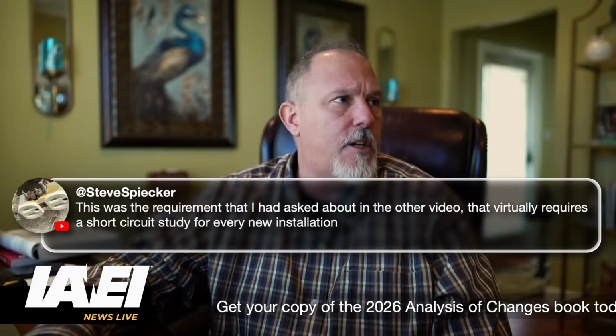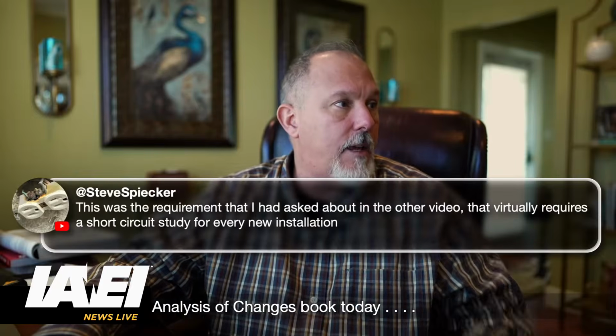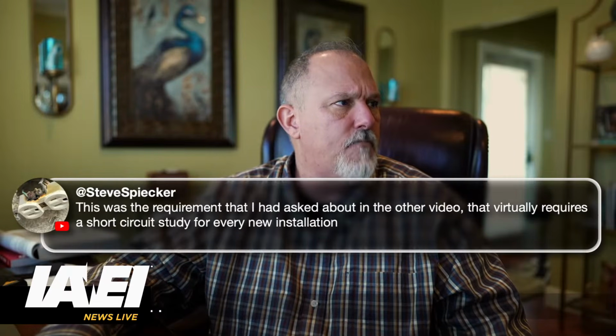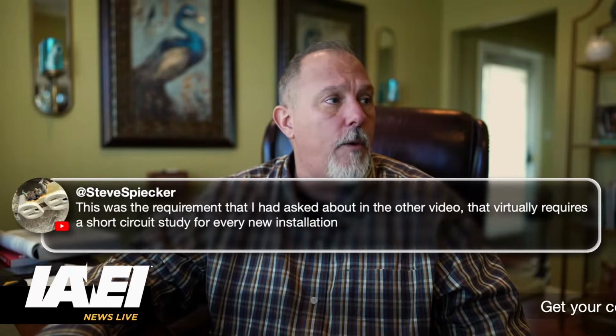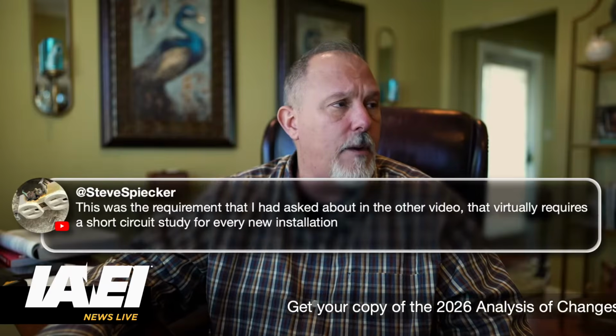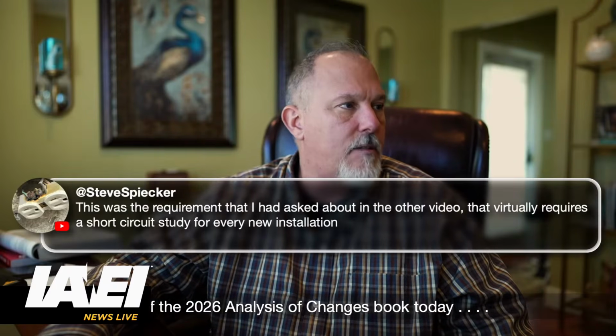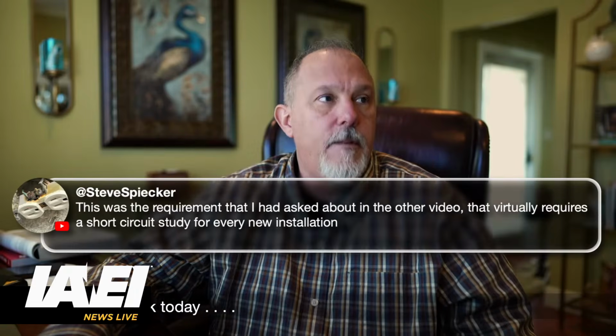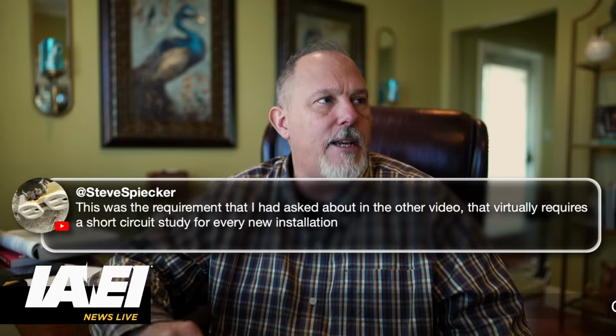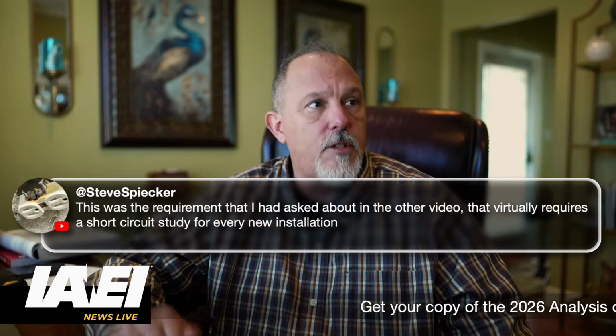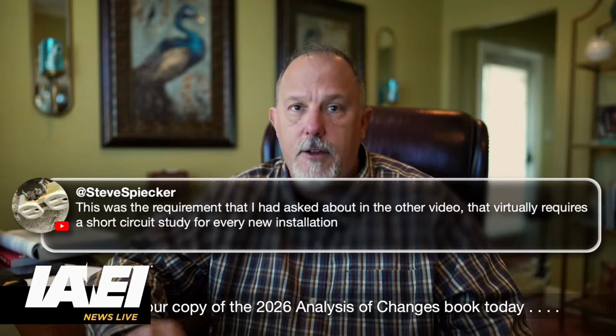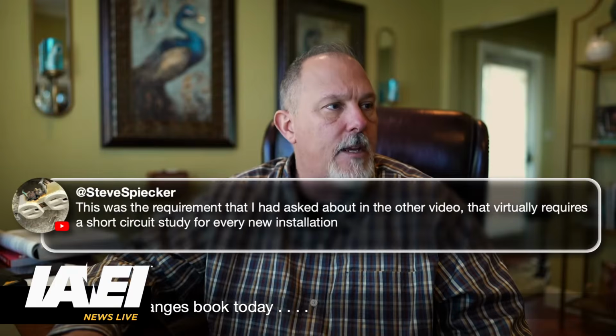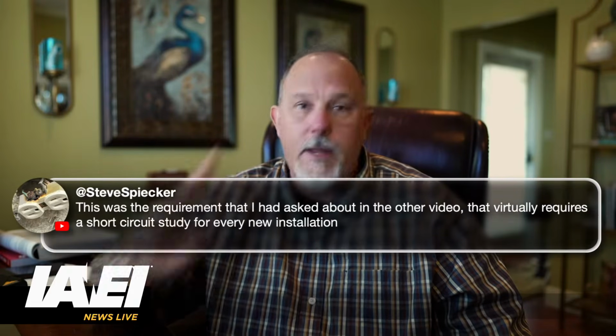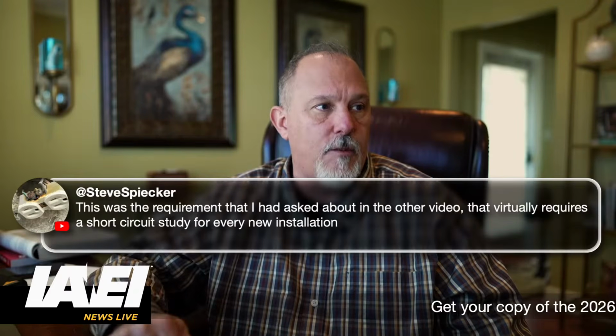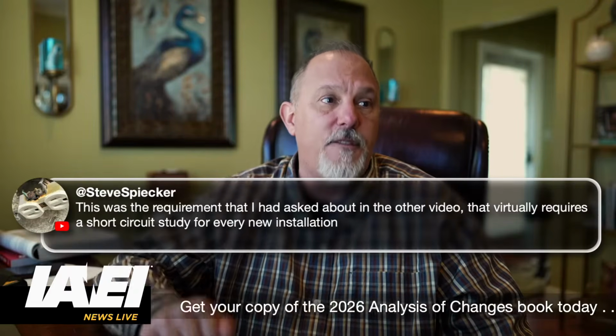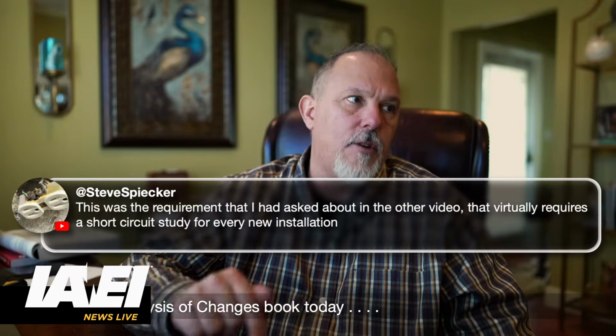If you look in the code, there's 408. Okay, let's take a look at 408. 408.8.4. My NFPA link is much, okay, short circuit current rating 408.6. Take a look at 408.6. It says switchboards, switchgear, and panelboards shall have a short circuit current rating not less than the available fault current in other than 1 and 2 family dwellings, and it says shall comply with the following. Item 1, the available fault current at the line terminals and the date the calculation was performed shall be field marked in a readily accessible location in the enclosure at the point of supply.